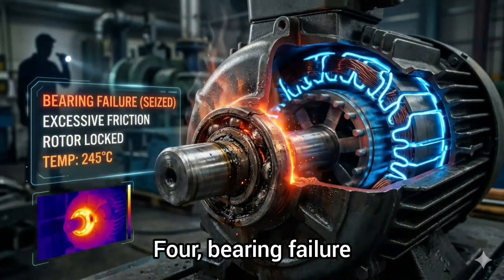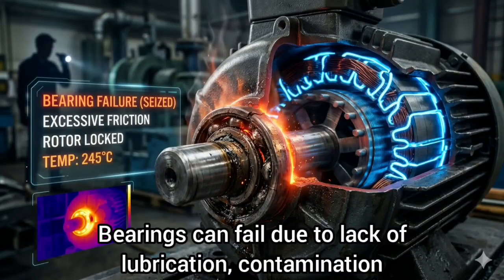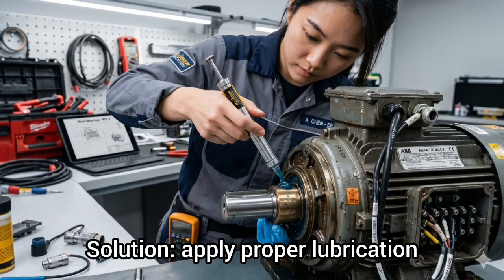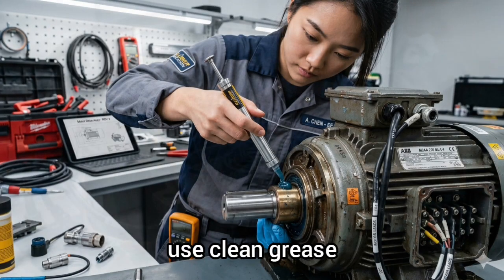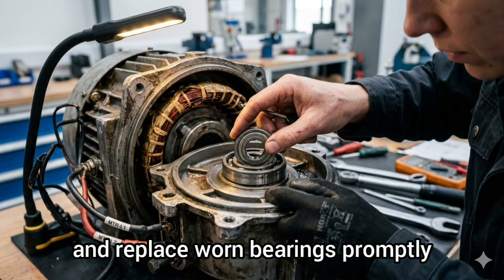4. Bearing failure. Bearings can fail due to lack of lubrication, contamination, or excessive load. Solution: apply proper lubrication, use clean grease, and replace worn bearings promptly.